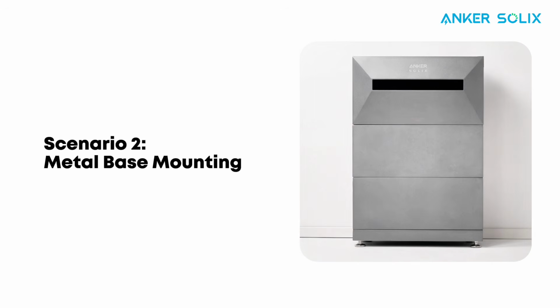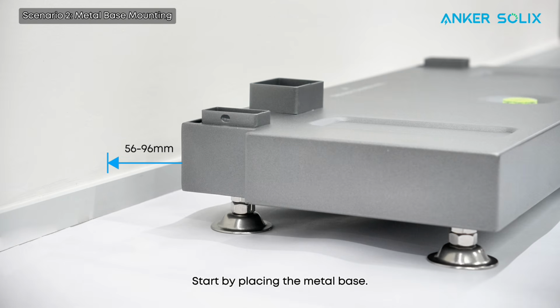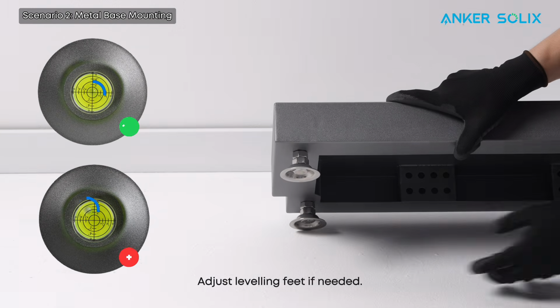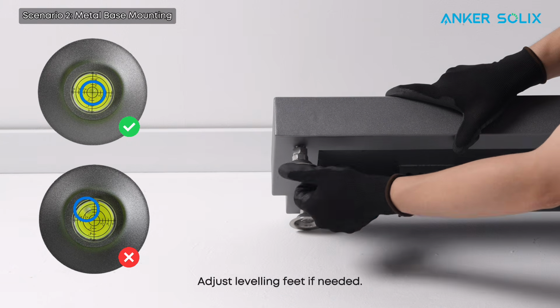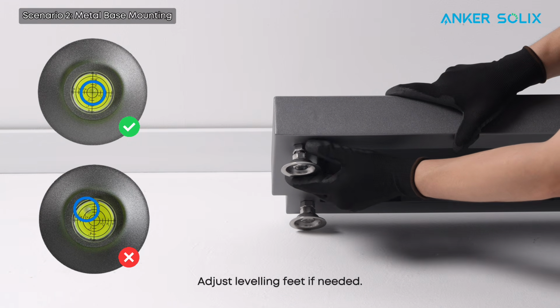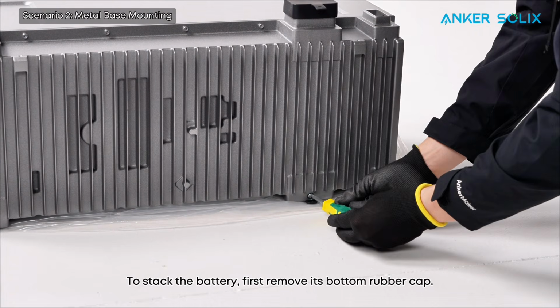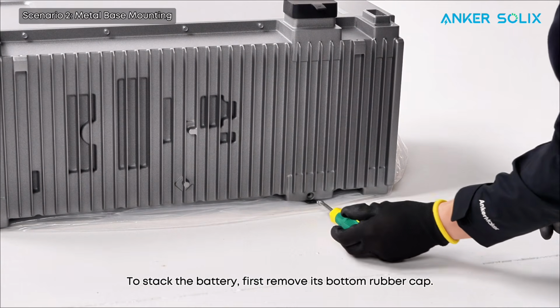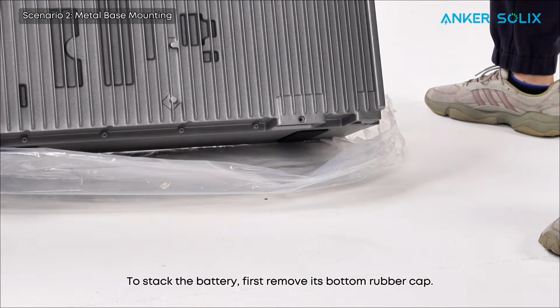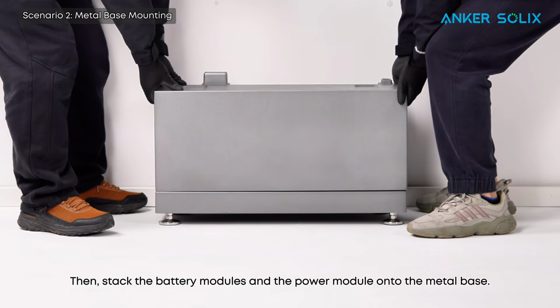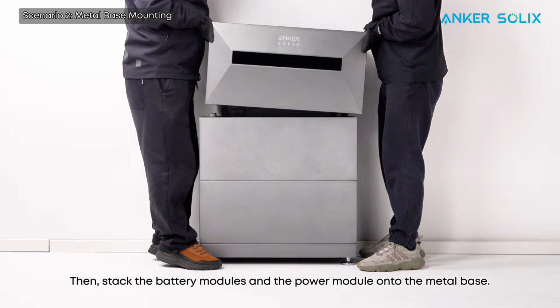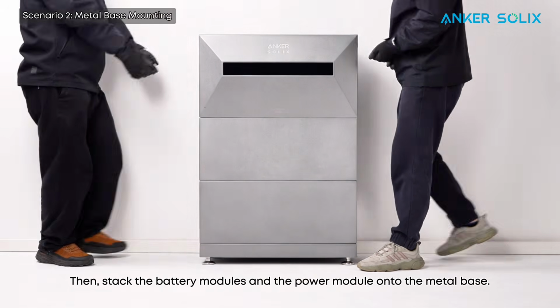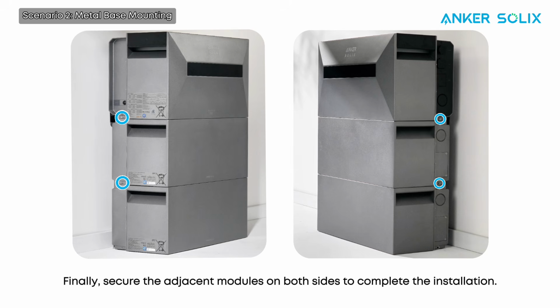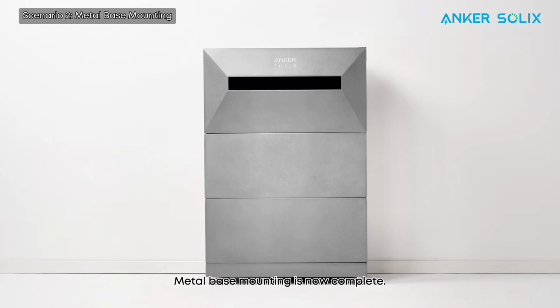Scenario 2. Metal base mounting. Start by placing the metal base. Adjust leveling feet if needed. To stack the battery, first remove its bottom rubber cap. Then, stack the battery modules and the power module onto the metal base. Finally, secure the adjacent modules on both sides to complete the installation. Metal base mounting is now complete.